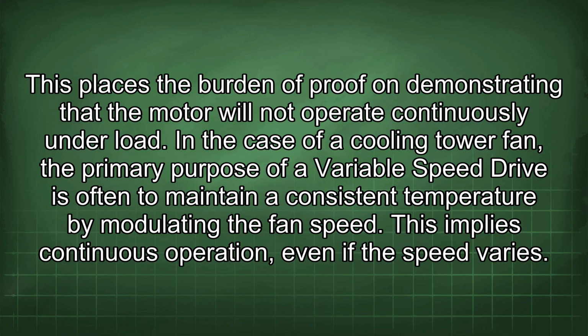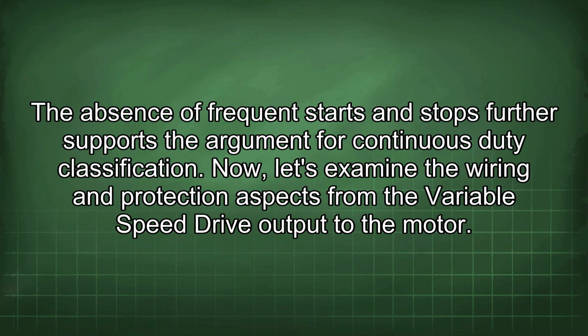In the case of a cooling tower fan, the primary purpose of a variable speed drive is often to maintain a consistent temperature by modulating the fan speed. This implies continuous operation, even if the speed varies. The absence of frequent starts and stops further supports the argument for continuous duty classification. Now let's examine the wiring and protection aspects from the variable speed drive output to the motor.